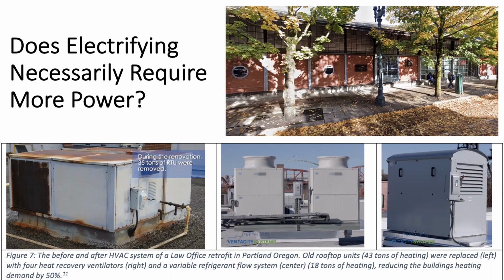So they're able to downsize the amount of heat pumps that go in, put in energy efficiency, and there's no effect on the electrical service. This turns out to be pretty common in big commercial buildings — they have old systems, 40 years old, big systems. And the new stuff is so efficient, along with LED lights and putting in an energy recovery ventilator, which is a newish strategy. It's so efficient there's no new extra power needs, even though you're doubling up and putting in space heating and perhaps domestic hot water too.